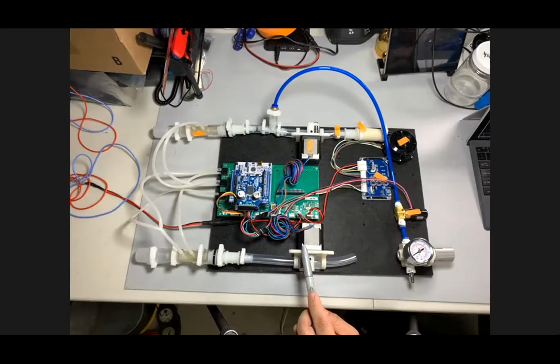And this pinch valve allows us to control the back pressure of the exhale from the patient, which is what allows us to deliver a controlled PEEP, positive end expiratory pressure. It's a minimum pressure that we maintain in the patient's lungs to keep the alveoli from collapsing, and it's an important feature of the ventilator, something for us to provide.